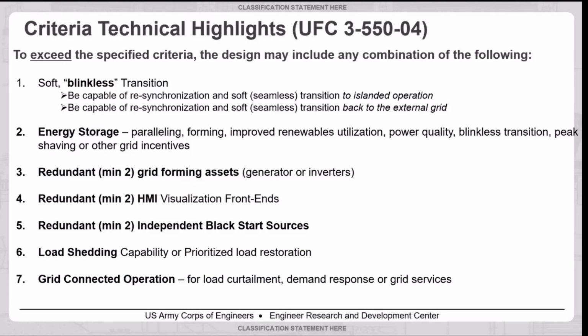Energy storage is a very controversial topic within much of the DoD. The UFC for energy storage says that any grid scale lithium ion batteries cannot be placed in an occupied facility, nor can they be placed within 100 feet of an occupied facility. Figuring out where to site them within some of our more space-constrained installations has proved pretty challenging. There was a group during the discussions saying you have to contain energy storage to be a microgrid. No, you don't have to. It's nice to have, but you don't have to.